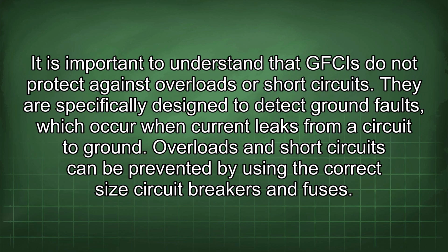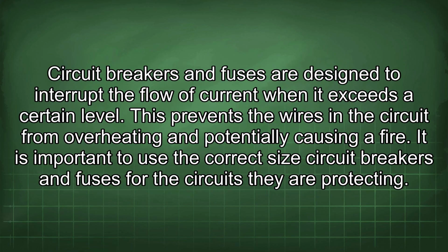It is important to understand that GFCIs do not protect against overloads or short circuits. They are specifically designed to detect ground faults, which occur when current leaks from a circuit to ground. Overloads and short circuits can be prevented by using the correct size circuit breakers and fuses. Circuit breakers and fuses are designed to interrupt the flow of current when it exceeds a certain level. This prevents the wires in the circuit from overheating and potentially causing a fire.